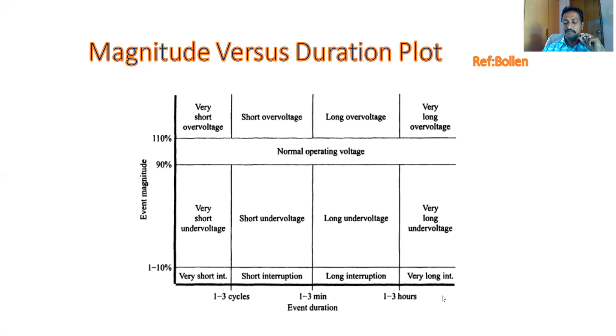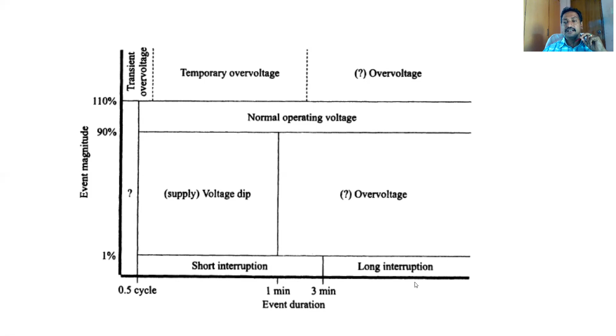Similarly, we'll go to this transient power voltage. Below 0.5 cycles, only transients are obtained. Above 0.5 cycles, a power voltage variation or over voltage will be obtained. So below 0.5 cycles, above 110% is called transient over voltage, and from 0.5 cycles to 1 minute, temporary over voltage, more than 110%. Less than 90% is voltage dip, also called supply dip. If it is more than 1 minute, above 110%, over voltage; below 90%, under voltage. Sorry for this, this is under voltage. And below 10%, long interruption.